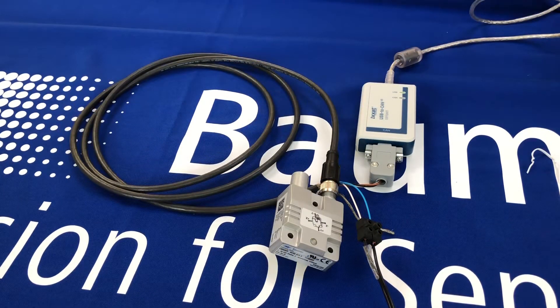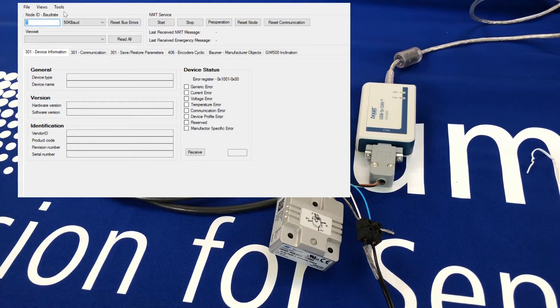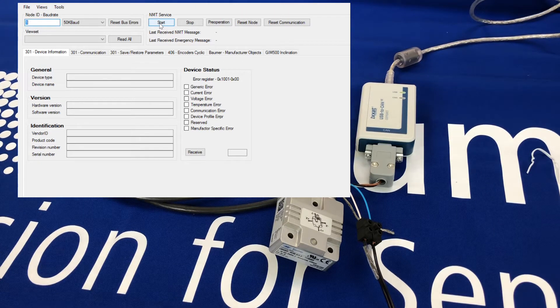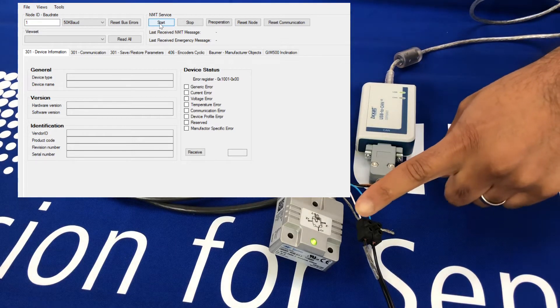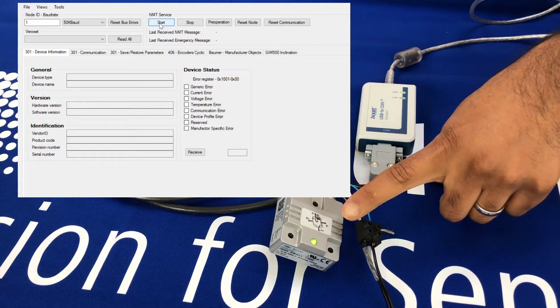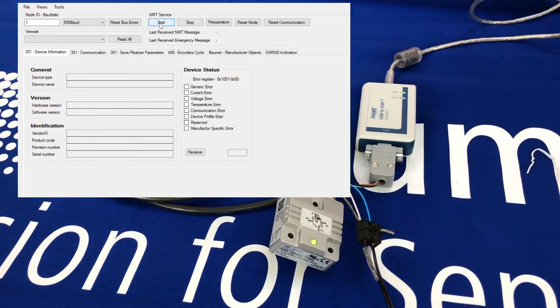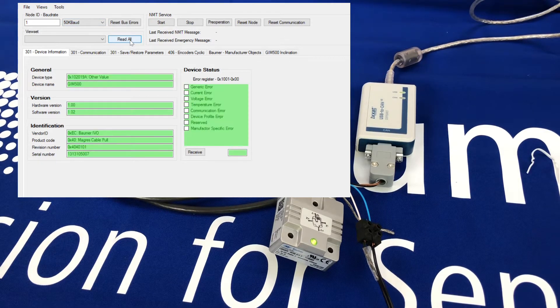I've connected the sensor via USB-to-CAN interface to my PC. I can open this CAN master piece of software, and if I press start on the NMT service, you'll see that the blinking on the LED of the sensor is now steady green — it means the sensor is active and able to read the information. You can see that the baud rate is the standard 50k baud from the sensor itself.